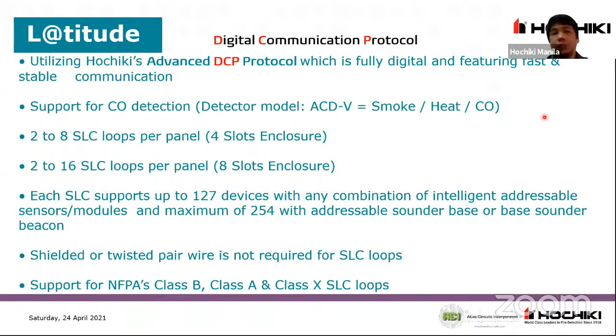So in terms of wiring ng SLC natin, shielded or twisted pair is not required for SLC loops. So kahit hindi tayo gumamit ng shielded or twisted pair. Pero meron tayong indicated sa NFPA 72 na in Level 2 na protection ng pathway, dapat is nakakabit tayo ng fire-rated na cable. Okay? Support NFPA's Class B, Class A, and Class X SLC loop. So yung dinescribe natin a while ago, so it's supported yan ng Latitude panel.